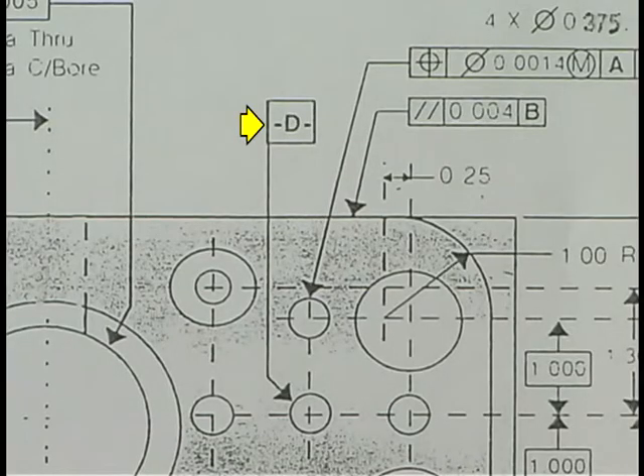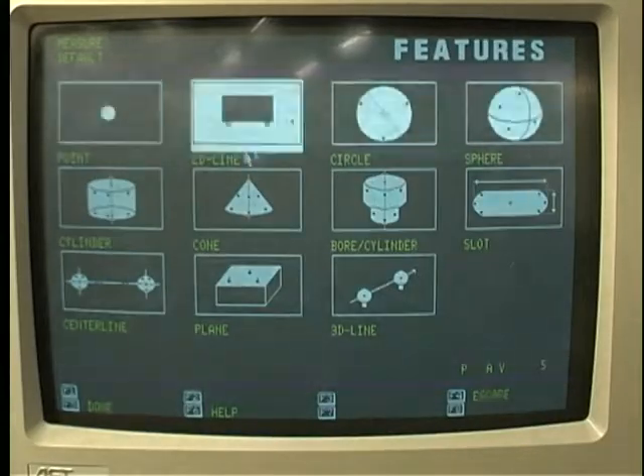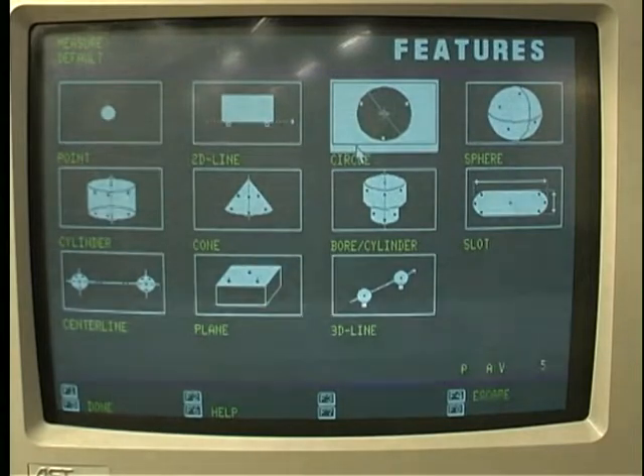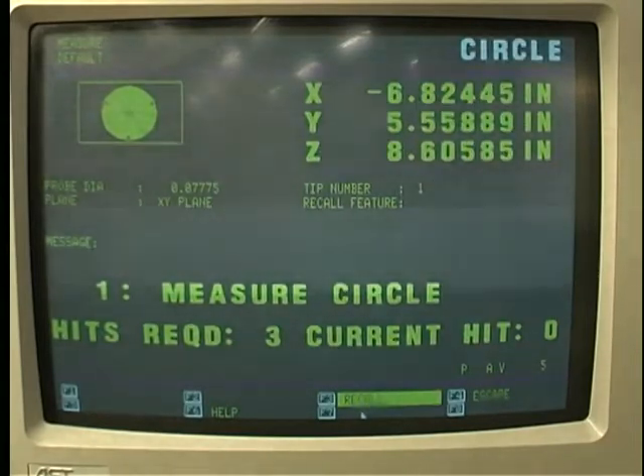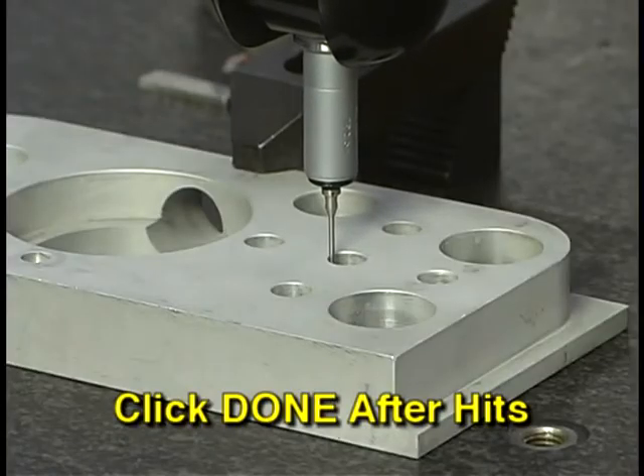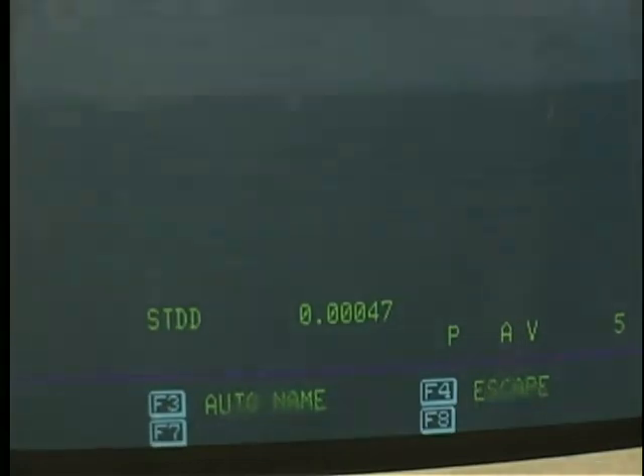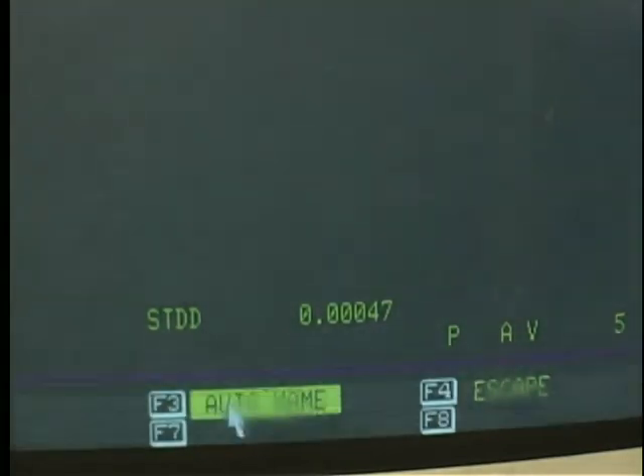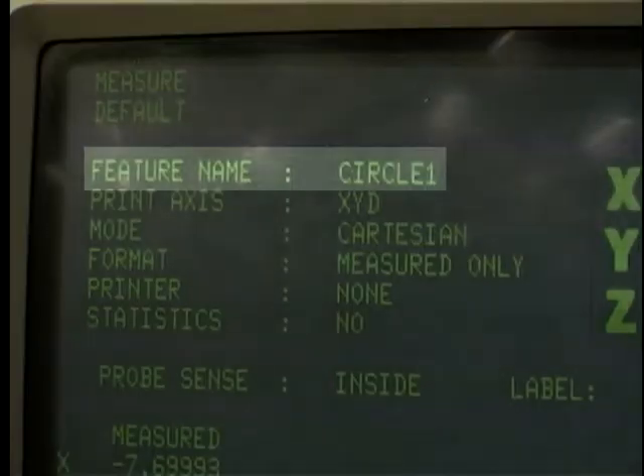The third axis to be established is datum D. Select measurements again. Since datum D is the center of a hole, circle selection is used. While three hits must be taken to locate the hole center, four are taken to get the standard deviation. Click done to complete the calculation. After the hits are completed, check the deviation. Auto name the feature and it will be circle 1.